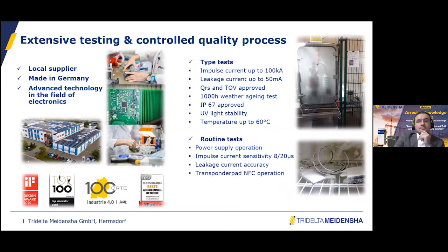So there are several current wave shapes that have been tested, discharges up to 100 kA. We have the same duty from QRS test and TOV tests applied to the smartCOUNT, weather aging tests and UV stability tests and some temperature cycling tests, IP protection tests, everything that is necessary to verify the operation under severe conditions. And then, of course, it is necessary to perform routine tests on each single device that is produced.